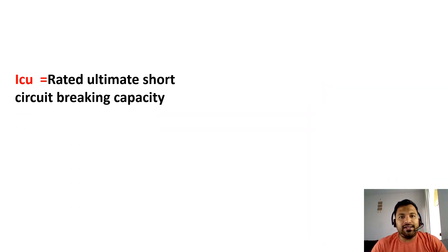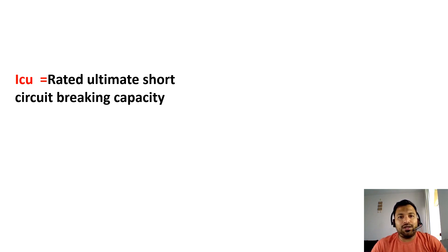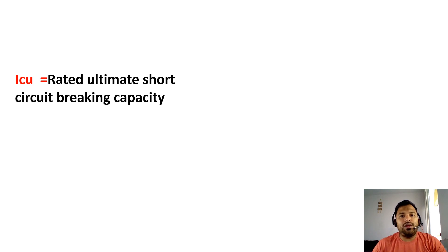Now we will see the ICU current. What is ICU current? ICU current is the ultimate short circuit breaking capacity. From the name itself, it is understood that the breaker will operate at the ultimate short circuit current. During a short circuit, enormous current will flow, and we are providing a circuit breaker to interrupt this short circuit current. So we have to know that, for example, this circuit breaker can carry 100 kiloamperes of short circuit current, and accordingly we choose our circuit breakers.